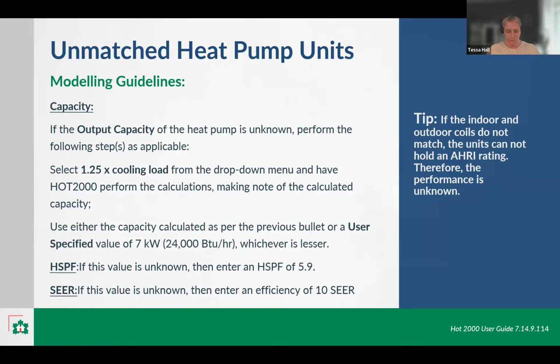So all your windows, insulation values, everything else, your air tightness test has been done, you're going to go into Hot 2000, select it as the 1.25 cooling load, which is the default setting we're supposed to model at the beginning anyway, and run a calculate. That calculate is going to tell us how many BTUs Hot 2000 thinks we need for that system.